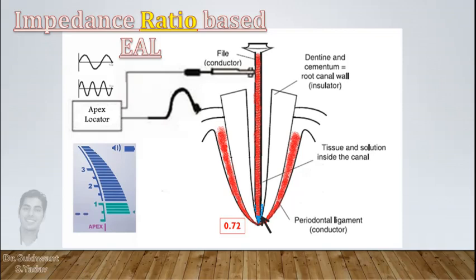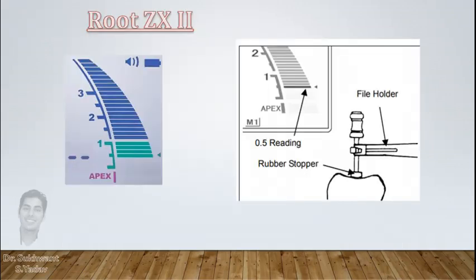Impedance value can differ in different canal contents but ratio remains always same. So Root ZX2, which is third generation apex locator, measures impedance ratio at apical constriction which indicates 0.5 mark on screen, and when file reaches apex and meets the PDL, apex flashes on screen.